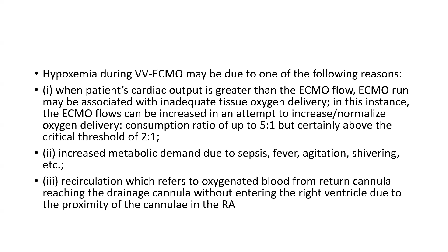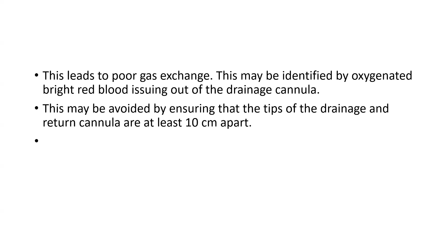Another reason for hypoxia is recirculation, which refers to oxygenated blood from the return cannula reaching the drainage cannula without entering the right ventricle, due to proximity of the cannulas in the right atrium. This leads to poor gas exchange. This may be identified by oxygenated bright red blood issuing out of the drainage cannula. And this may be avoided by ensuring that the tips of the drainage and the return cannula are at least 10 centimeters apart.